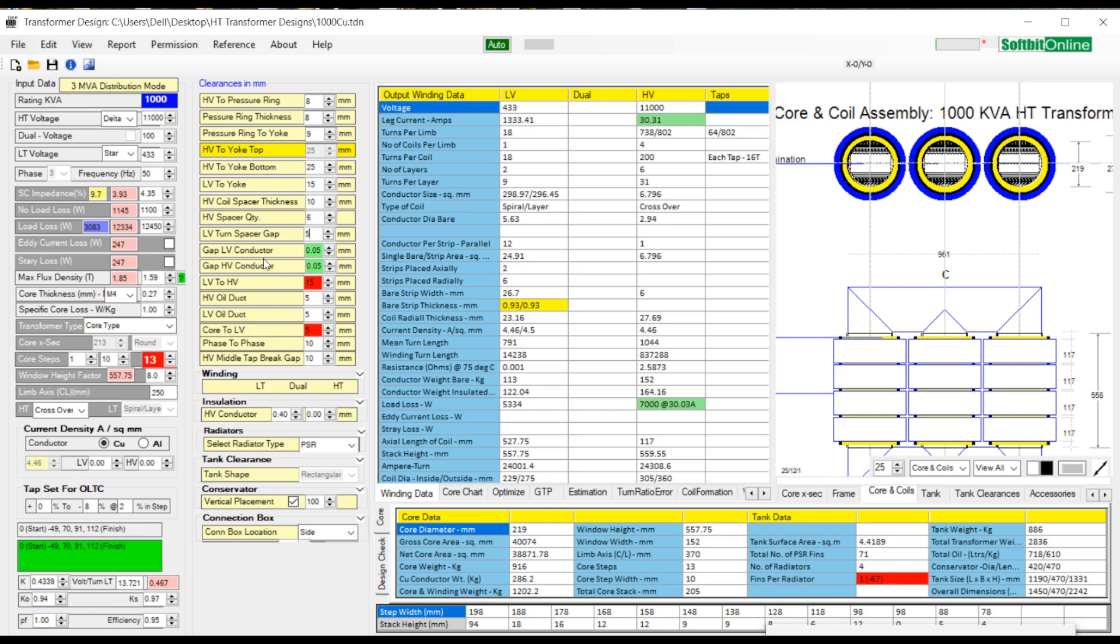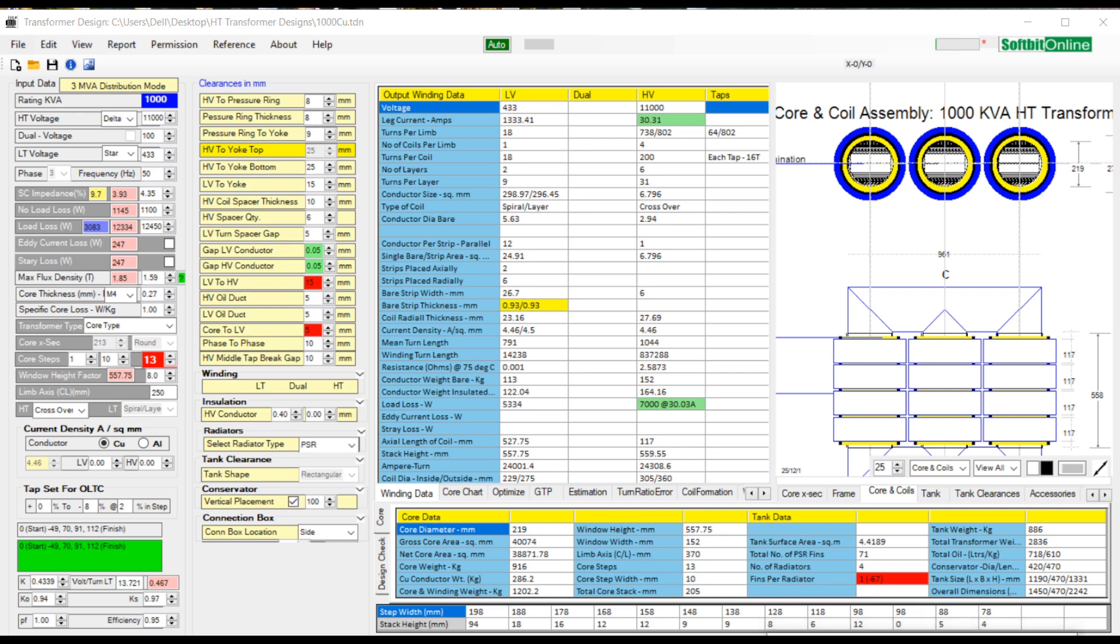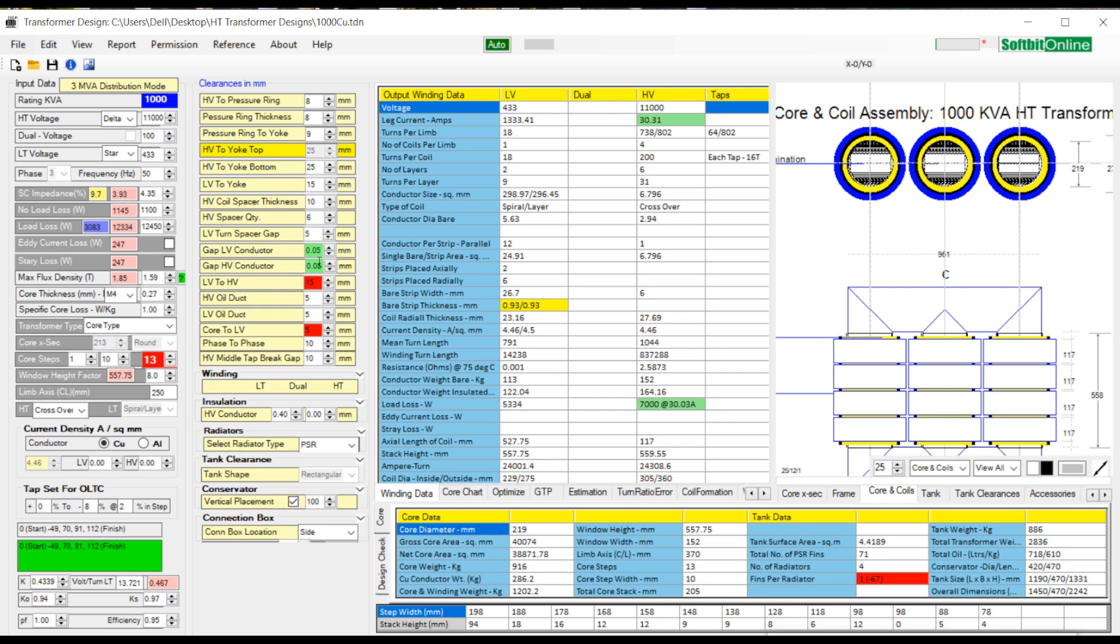While the winder in the winding section is making LV and HV coils, he comes across a problem of uneven wire or strip length because of insulation or for some other reason, then he has to give some gap between each turn in HV and LV coils. This is called gap LV conductor and gap HV conductor. This can also be considered as working clearance. A value of 0.25 mm is sufficient for these gaps, but you can increase this value as per your requirements.